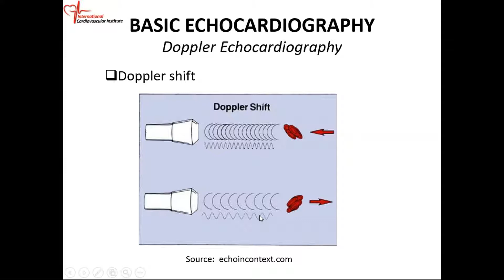When you have your ultrasound transducer, or your probe, remember the sound wave that you produce is going to travel in a straight line. If the blood is moving like that, then the ultrasound beam is going to make an angle with the moving red blood cells. This is the angle that we're talking about, theta. The ultrasound beam from the probe comes straight down, and the moving red blood cell moves horizontally. You want to make this angle as small as possible. If you can get the angle to be 0, that is what you're shooting for. If the angle is 0, then the ultrasound beam is going to be parallel to the moving red blood cell.